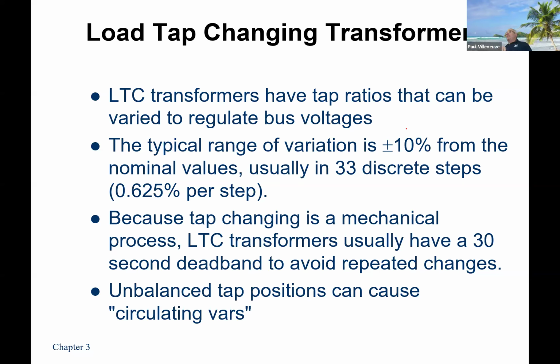Whereas the transformer that we looked at for the no load and open circuit test actually had no load tap changes, which means shut the transformer down completely, unbolt the cover, and then change the tap positions manually using a bunch of wrenches. Over here, it does it automatically. Very, very expensive, but much finer control. Instead of going plus or minus 5% in 5 steps, including the nominal, this can go plus or minus 10% in 33 steps. So each tap position is about 0.6%, whereas on the other one we had this morning it was 2.5%. So not nearly the resolution that you can have.